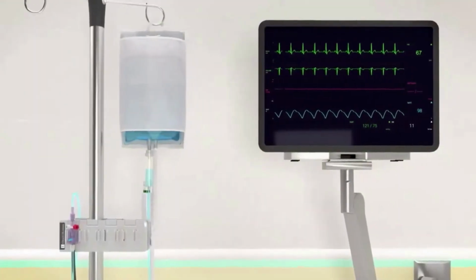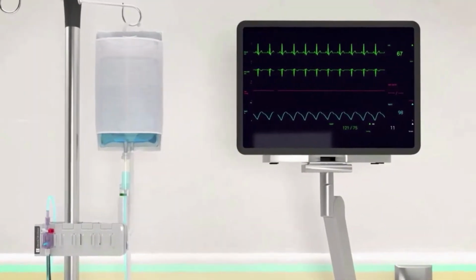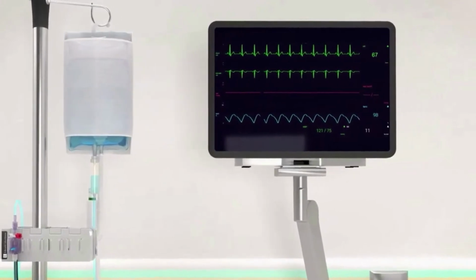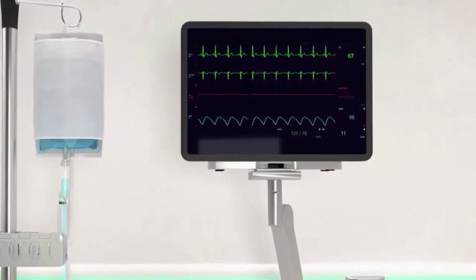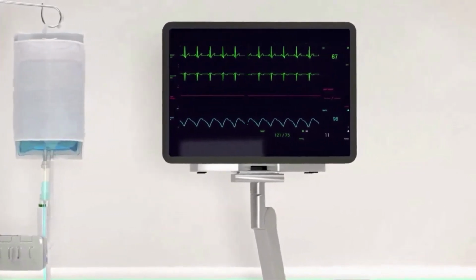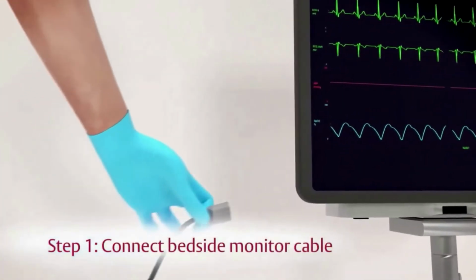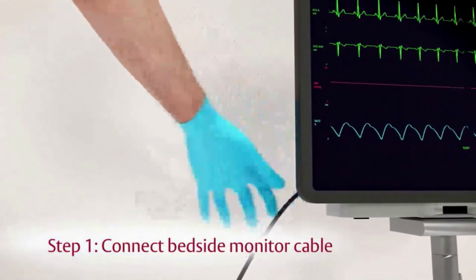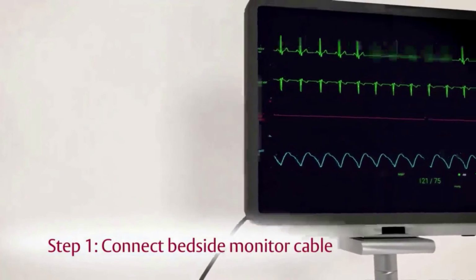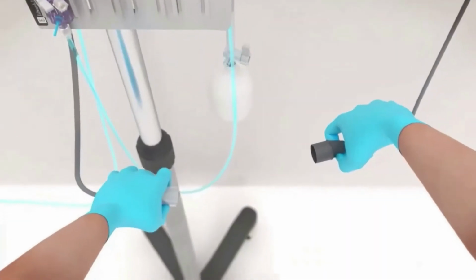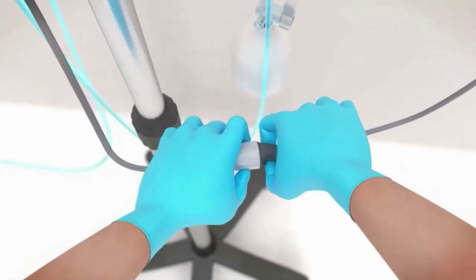Now that we have completed priming the system, we will need to calibrate the TrueWave transducer with the bedside physiologic monitor using the following 8 steps. Step 1. Connect the appropriate TrueWave reusable pressure cable to the proper port on the bedside monitor. Then, connect the opposite end of the reusable cable to the TrueWave transducer's white connecting cable.